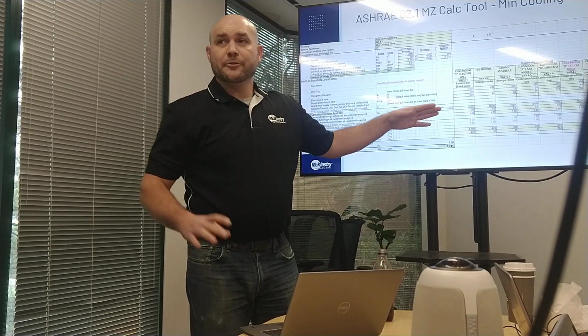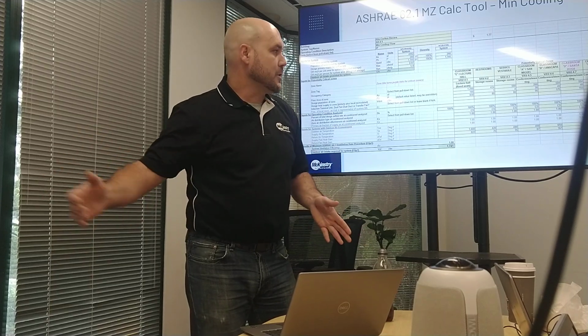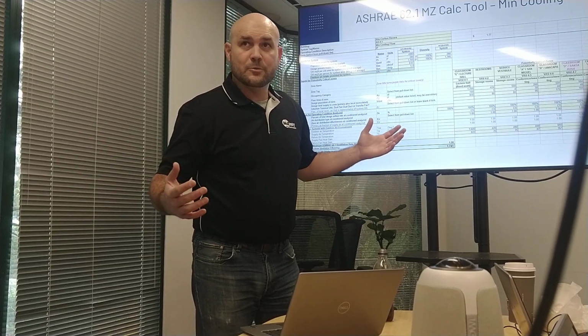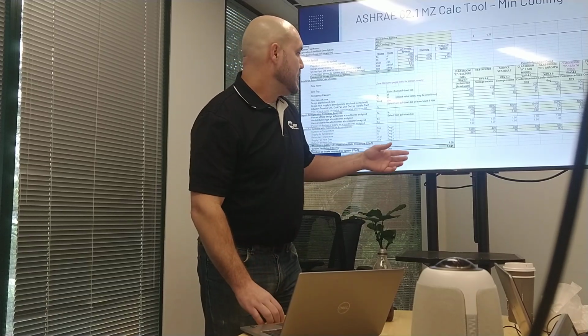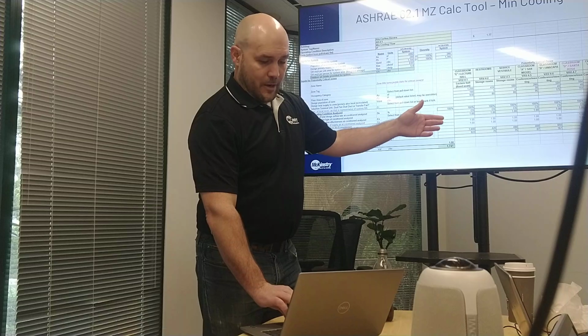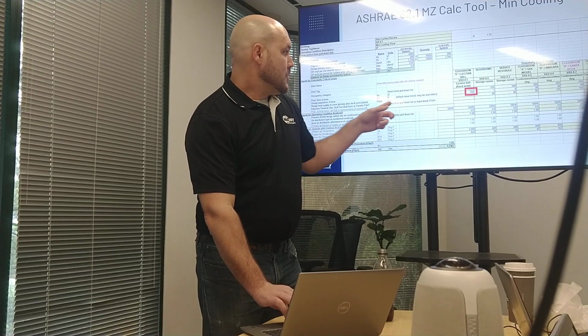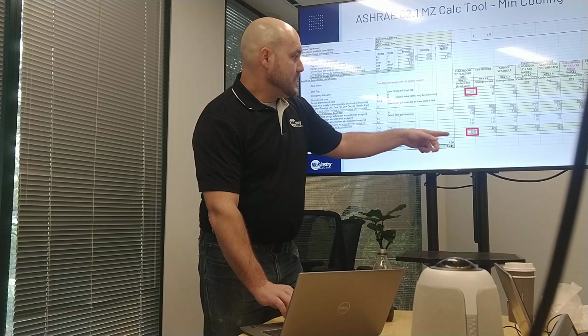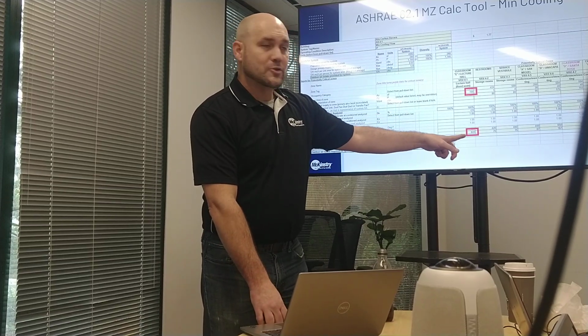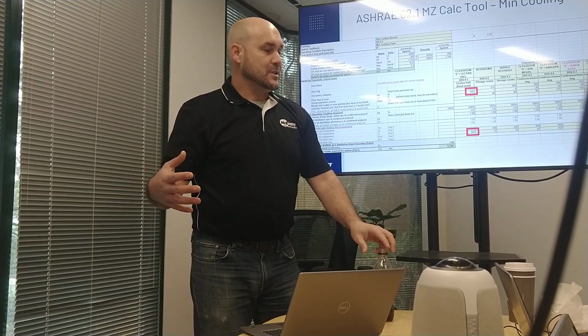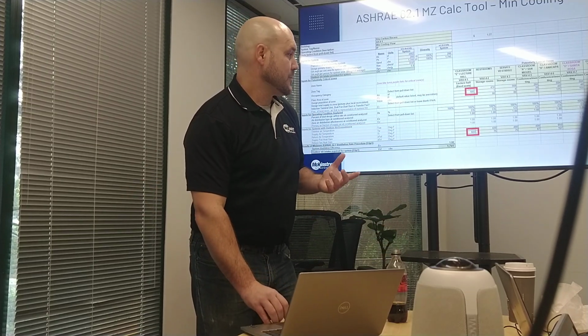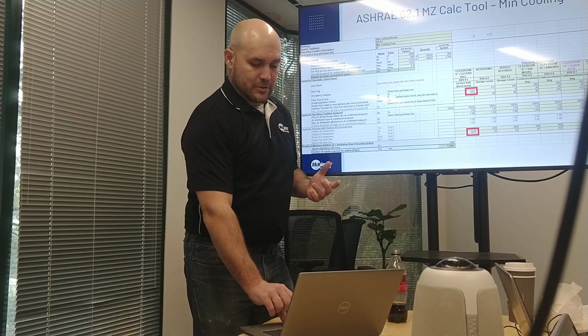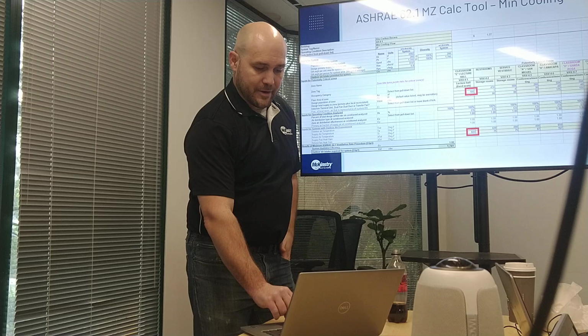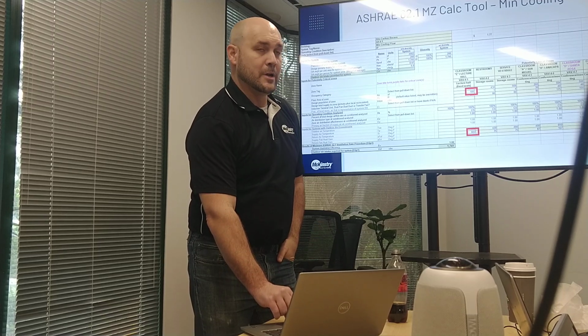They had this lecture hall with 100 fixed seats, like 10 rows, 10 seats across. So okay, zone population is 100, maybe 101 if there's a presenter. So 100 people is the zone population, and that means a minimum in cooling mode of 822 CFM based on the square footage of the room times the CFM per square foot, and then the 100 people times 5 CFM per person. So that gives 822 CFM in cooling mode.